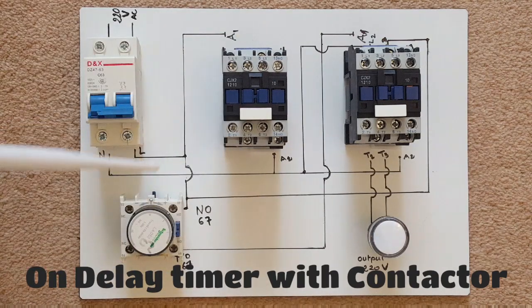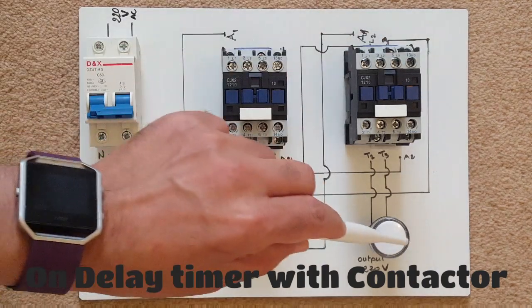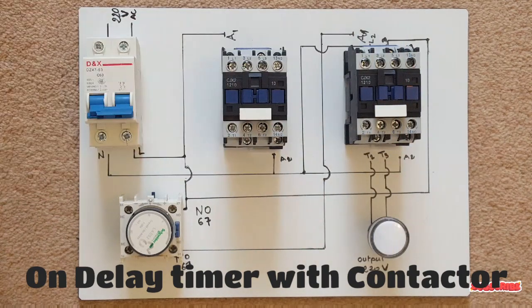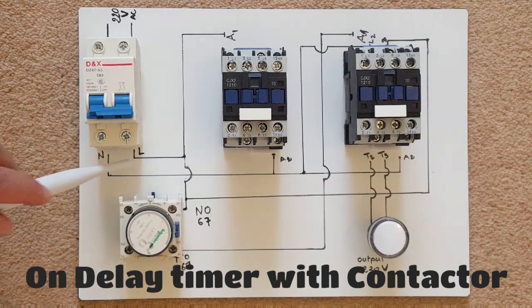Here we've got our on-delay timer, our circuit breaker, contactor number one, and contactor number two. We've got a light at 220V — that goes back to your property, that's the main supply to your property. It comes in at 220 volt AC, so we've got neutral and live. The live goes to A1 on contactor number one, and the neutral goes to A2 on contactor number one.